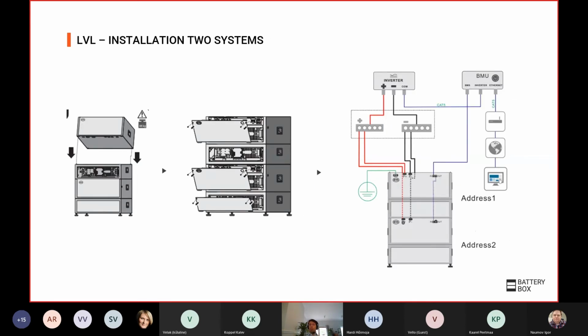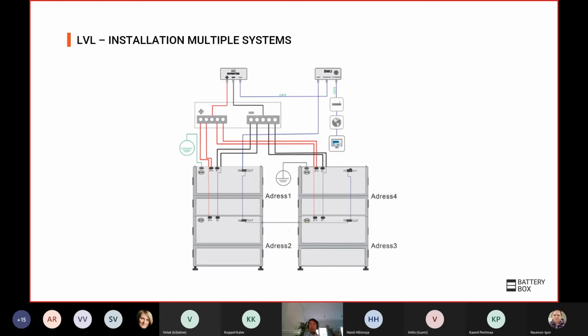When you put two batteries one on top of the other, in order to make the installation neater and to keep the cables more organized, you can have the power and communication cables going through the inside of the top battery towards the bottom battery. But always remember to use the same length and section of cable for each of the batteries going to the bus bar. When you have more units, you just need to make sure that you have a Cat5 communication cable going between all the batteries, from the out of the previous battery to the in of the current battery. And whenever you do the commissioning of the system, it will address them automatically.